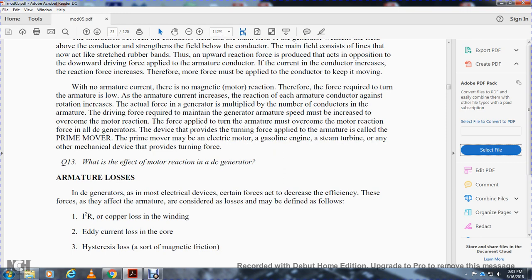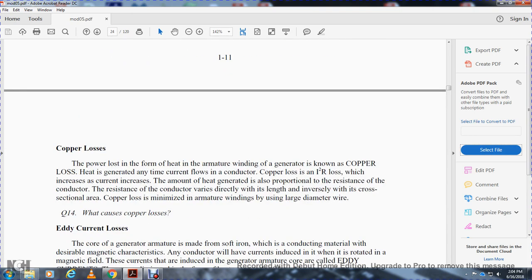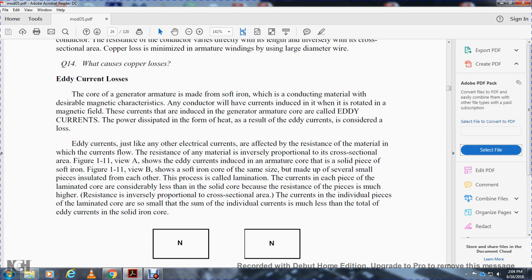Armature losses: in DC generators, as in most electrical devices, not all energy input is converted to useful output. Armature losses are defined as follows: copper loss (I²R loss) from armature winding resistance; eddy current loss in the armature core; and hysteresis loss from magnetic properties of the core. Copper loss is power dissipated as heat in the armature winding. It is proportional to the square of the current and to the resistance of the conductor — resistance varies directly with length and inversely with cross-sectional area. Copper losses are minimized by using large-diameter wire for armature windings. The core of the generator armature is made of soft iron, a conducting material with desirable magnetic characteristics. Currents are induced in the rotating armature core by the magnetic field — these are called eddy currents. The power dissipated as heat by eddy currents is considered a loss.